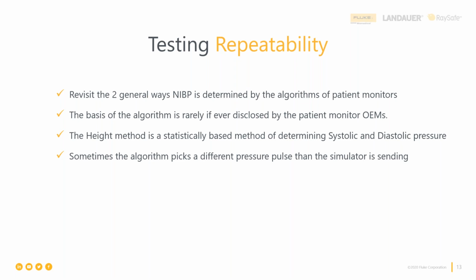And typically the manufacturer of the medical device will say that in their service manual test procedure as well. So we're going to look at accuracy separate from repeatability. We're going to look at other needs like leak tests. Is it able to hold a pressure? Things like that before we do either the accuracy or the repeatability test.